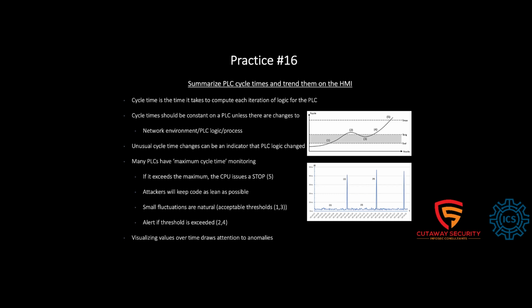It shouldn't change. However, if an attacker has added some code to the PLC and you were not able to recognize or identify that change elsewhere, this is maybe one way to monitor. Where you didn't do anything else or couldn't do any other practices, you're just monitoring the CPU cycle time. Any additional code will have an impact. It will increase the CPU time. And if you log it and monitor it as a trend on the HMI, in this example, every so often you have a spike, which shows that something is being executed at that time. That's another way to identify additional code or additional code execution on the PLC.